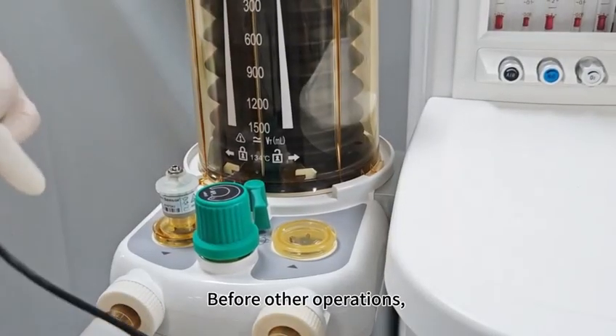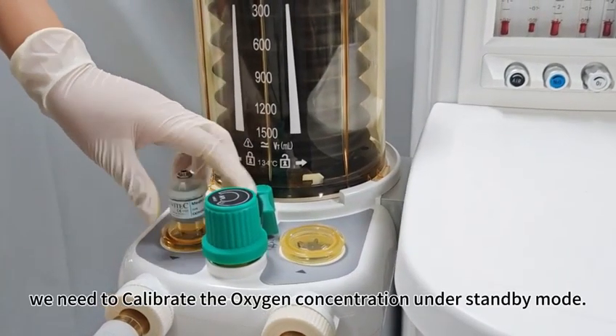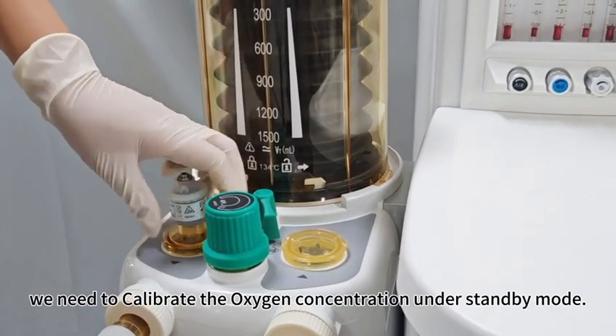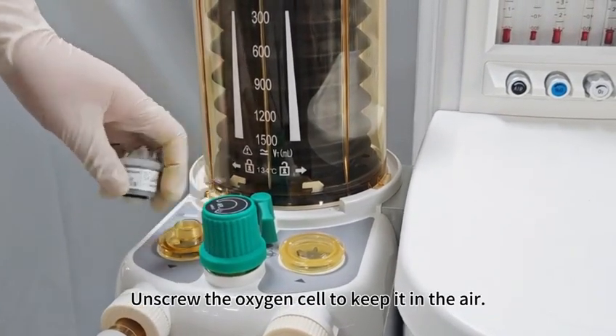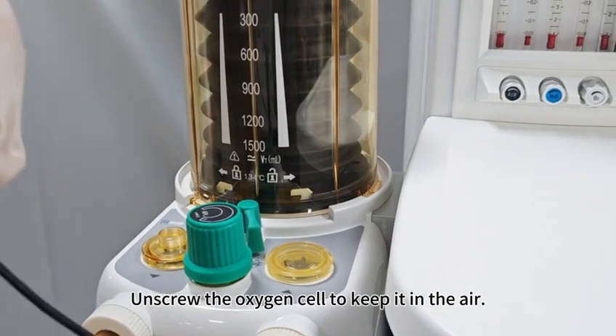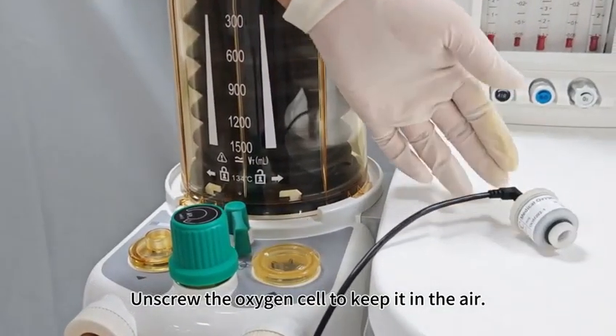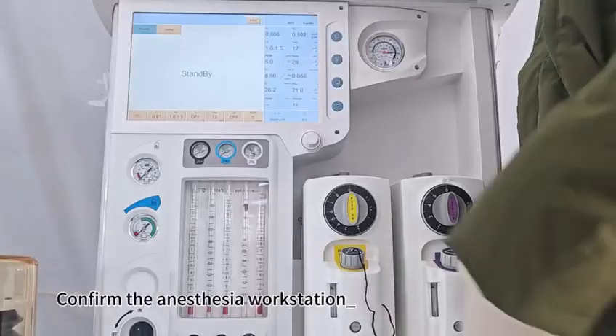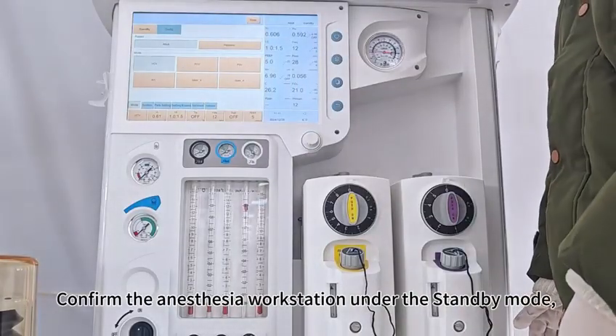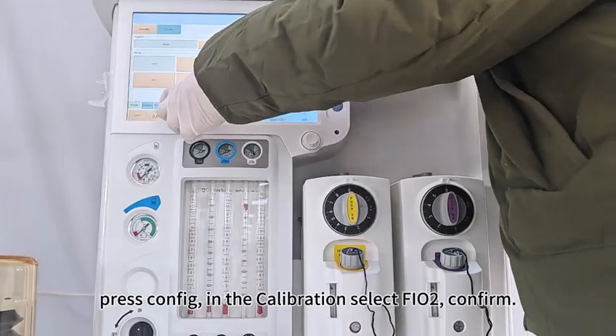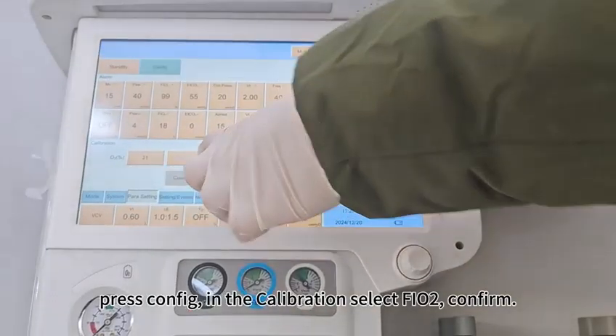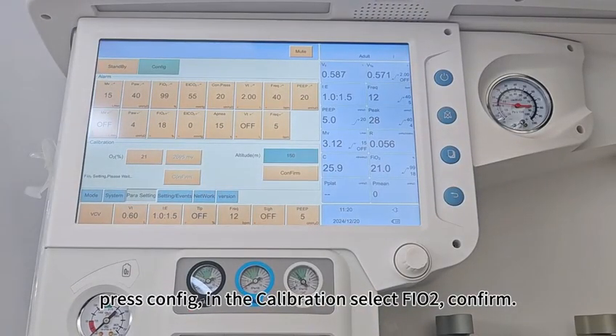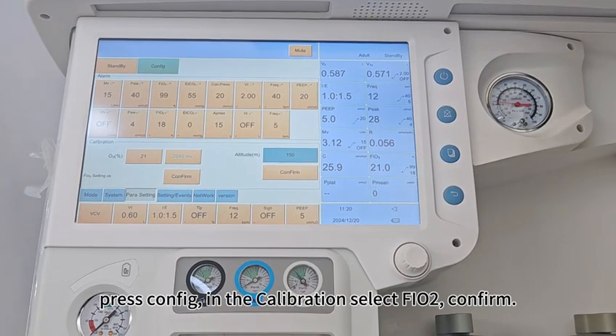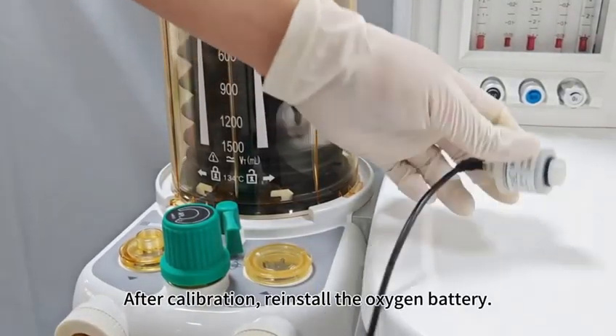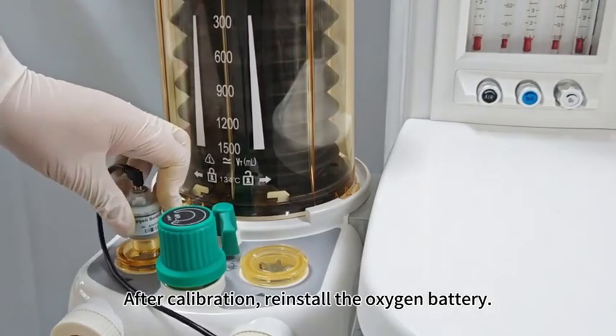Before other operations, we need to calibrate the oxygen concentration under standby mode. Unscrew the oxygen cell to keep it in the air. Confirm the anesthesia workstation under the standby mode, press config, in the calibration select FiO2, confirm. After calibration, reinstall the oxygen battery.